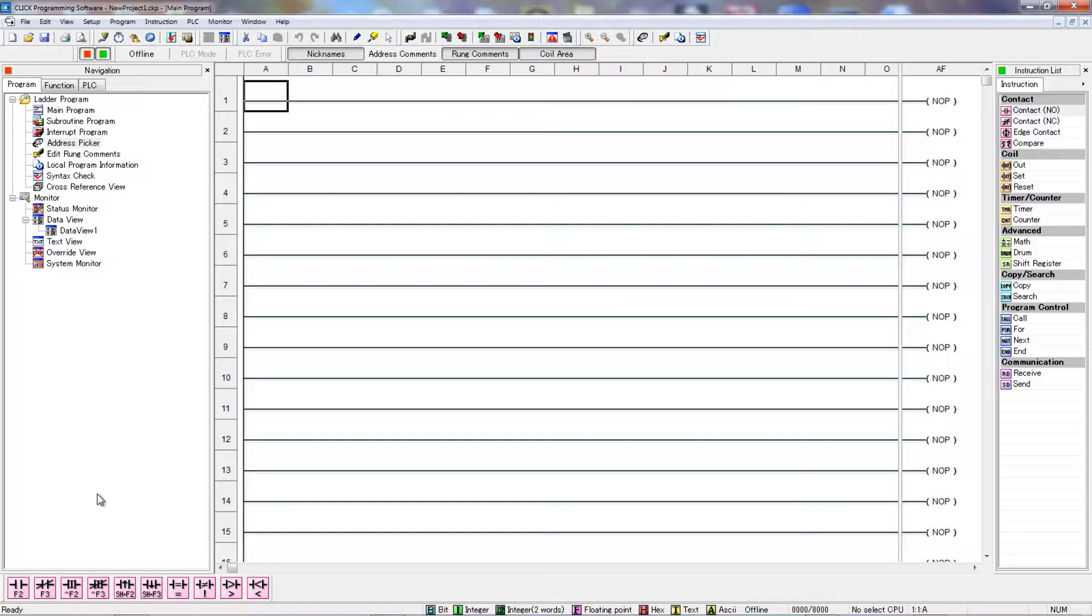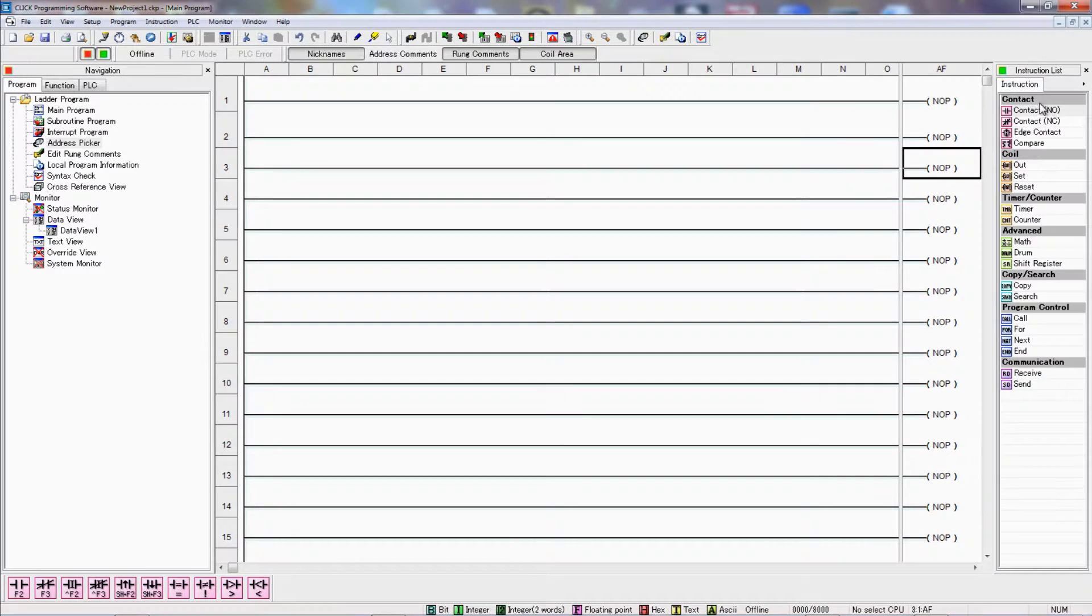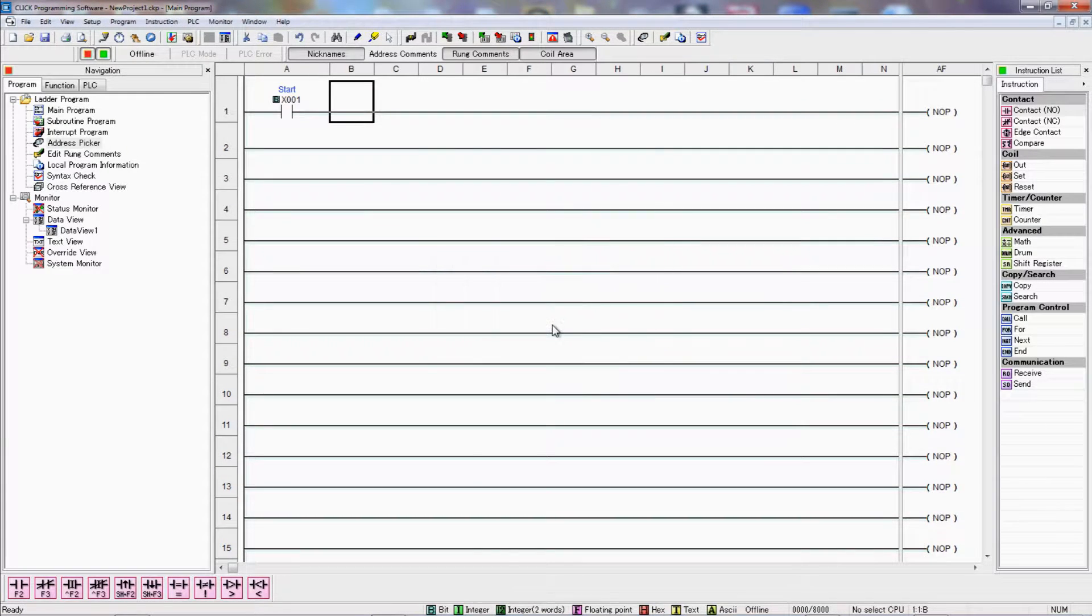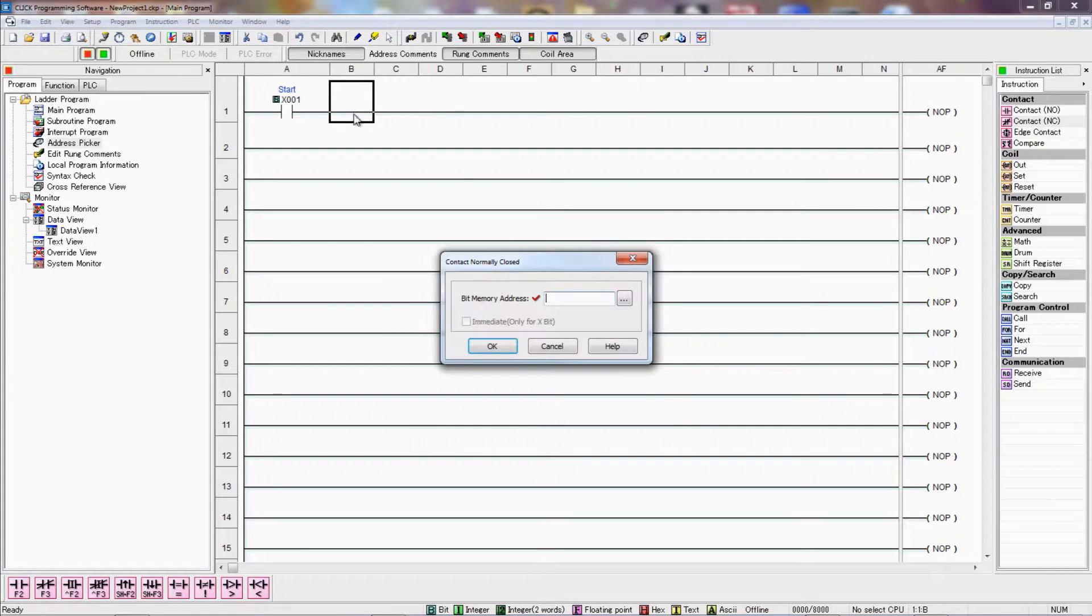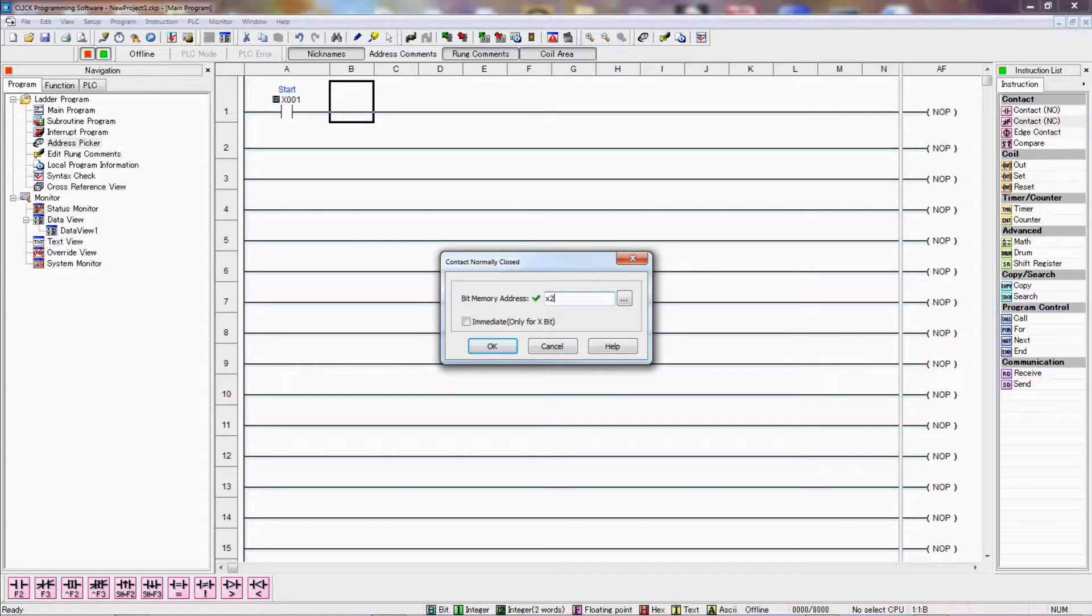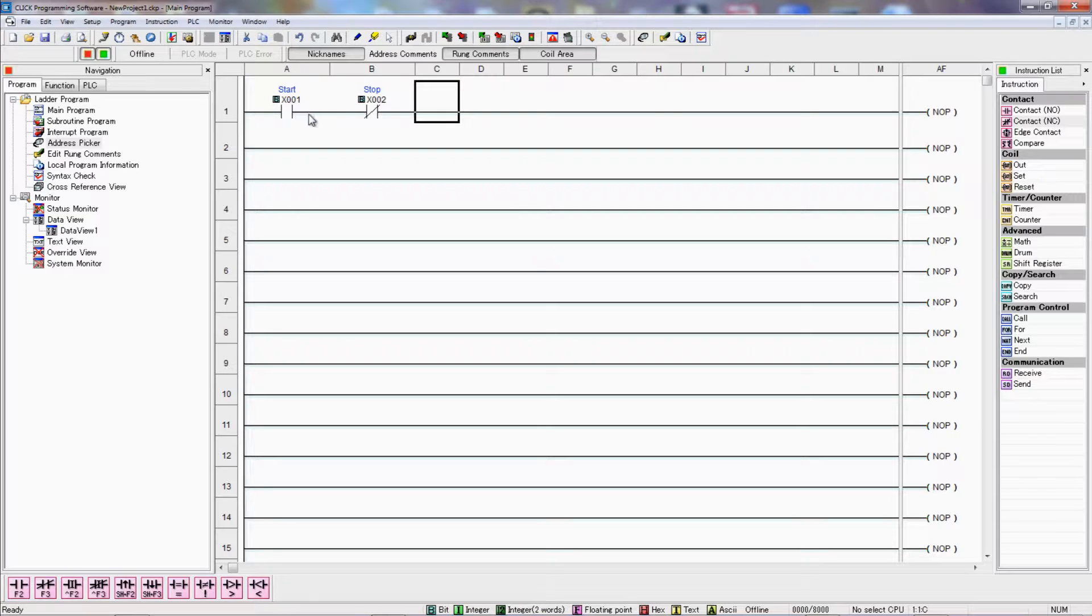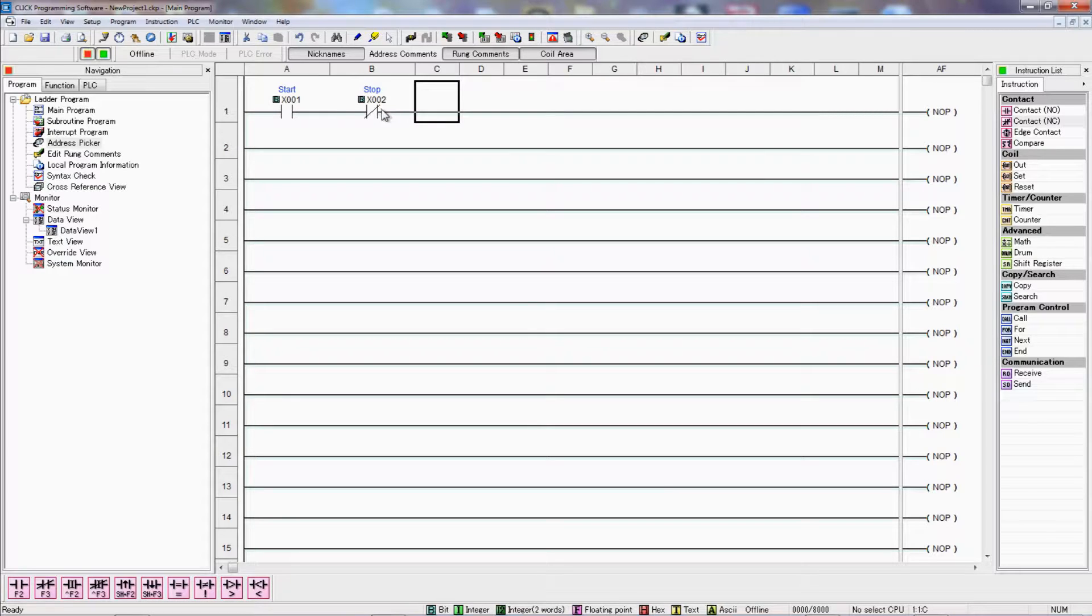Now we've got some shortcuts we can use down here. I've gotten used to using the keyboard shortcuts, F2, F3. But when you're starting out, you probably just begin by dragging these over. I'm going to kind of highlight it here with this little circle around the pointer. And we'll allocate this as X1, which I know is my start input that I just allocated earlier. I'm using a normally open contact here. For the stop contact, we're going to drag over a normally closed contact, which is X2. And unlike some more advanced systems, the Click only allows you to enter the contacts using its designation, the X designations and Y designations. You can't use these names that you allocate, start and stop, or whatever you want to call it, at least as far as I know. If somebody knows that there's a different way to do that, please let me know.